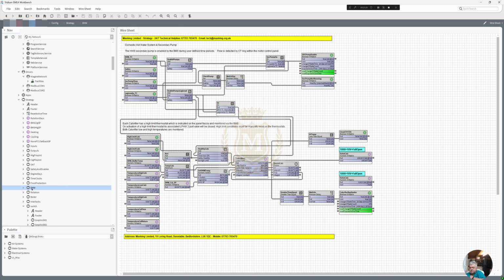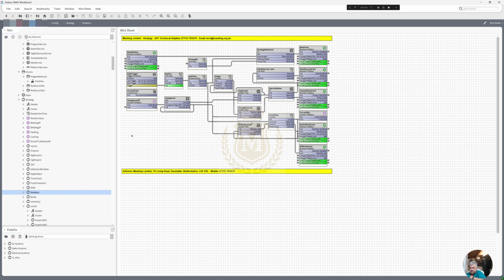Domestic hot water, it's a long time since I've seen this logic. Safety, Legionella, time clock. So I'm just having a quick look. Each calorifier has a high limit thermostat, yes. Okay, rotation, so I added a rotation folder. I normally build that into my pumps now. I normally don't have a rotation folder, but I've got one there. Reset button there. Software reset. So it looks like when we do a rotation, we also do a software reset on a trigger that I'm using, just in case anything's failed.